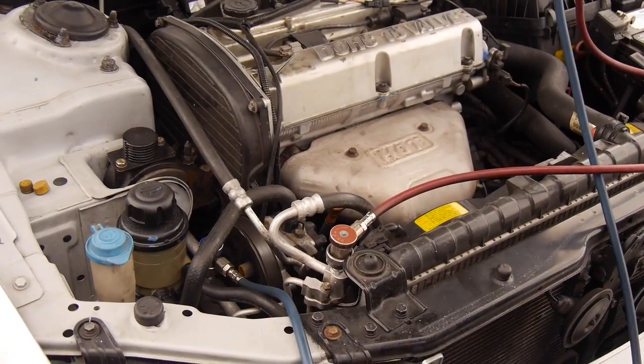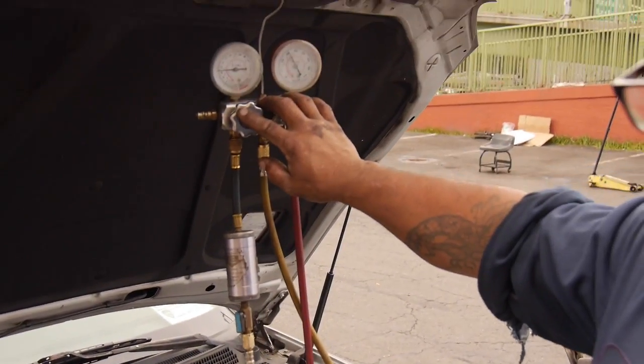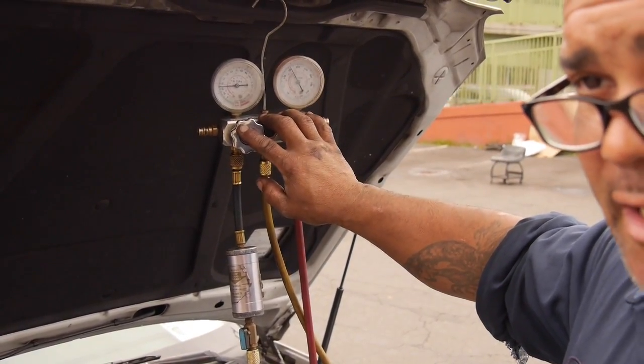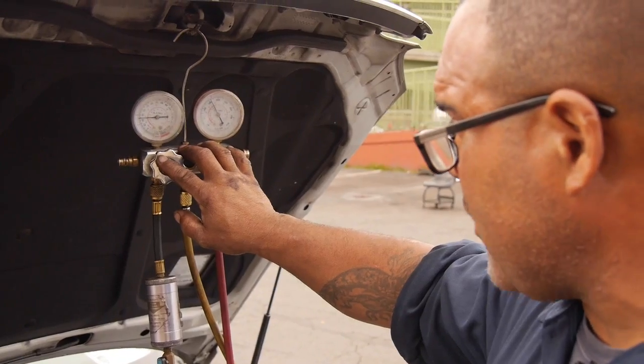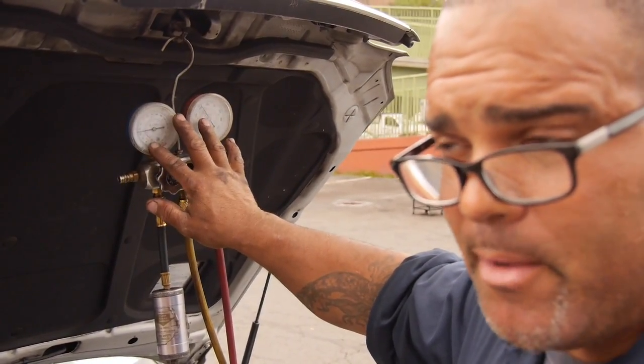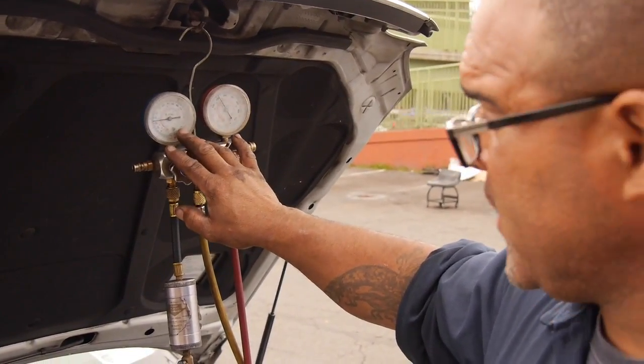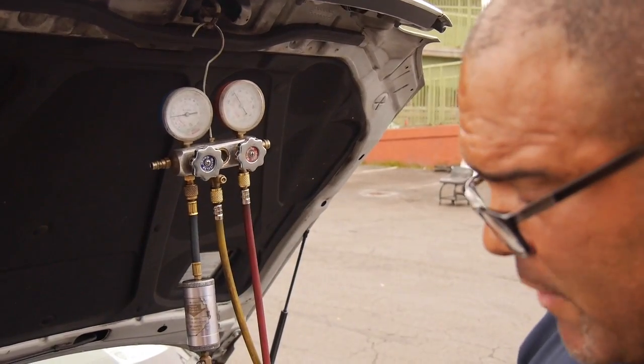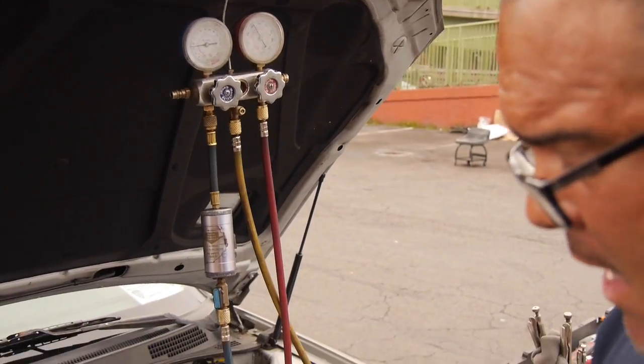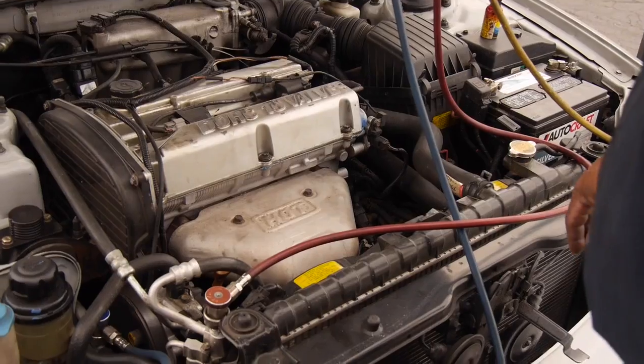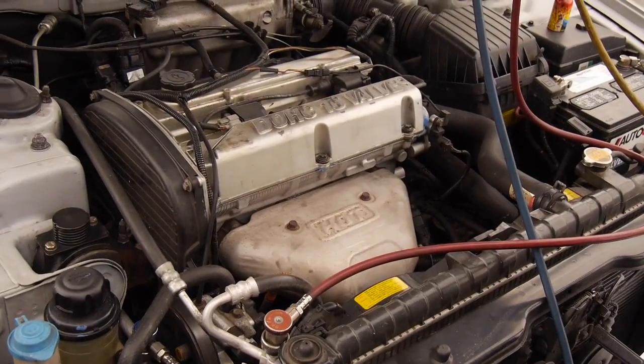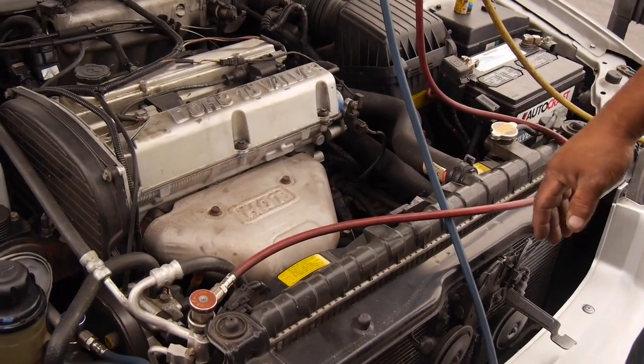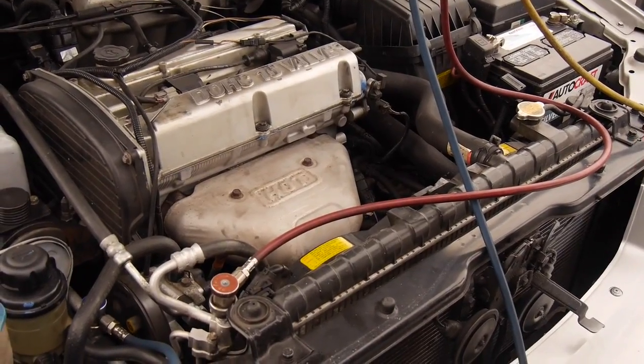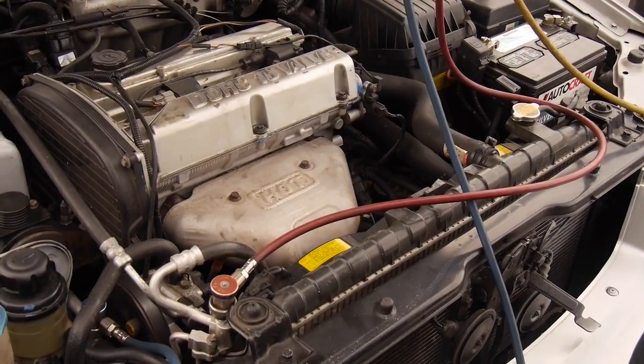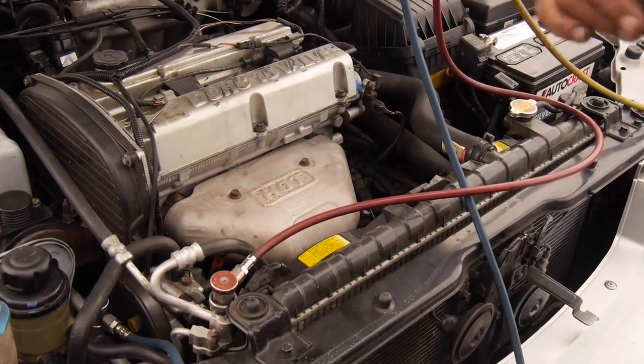And you monitor it for like 10, 15 minutes so you can get a true, accurate reading from the system. This will tell you if there's a problem internally, externally, electronically. You've got to look at the system overall. Right now, the system is running good. High side is good. Temperature is great here. This is excellent. I'm gonna bring my leak detector so we can start looking for leaks.